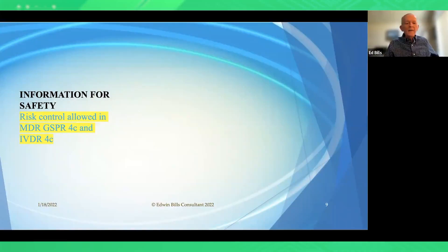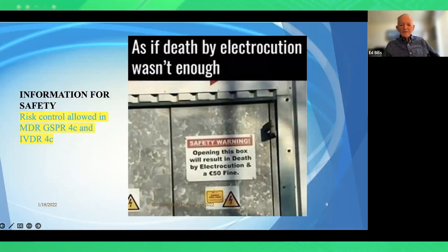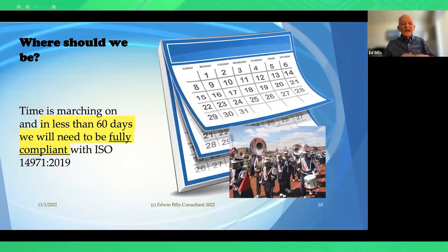One correction made in the MDR compared to the 2012 EN version is that information for safety is now allowed as a risk control measure in MDR. There's a humorous example shown of a dangerous warning sign. Time is running out: in less than 60 days from November 2022, organizations need to be fully compliant with ISO 14971-2019. Anything referencing an older edition needs to be gone by the end of December.